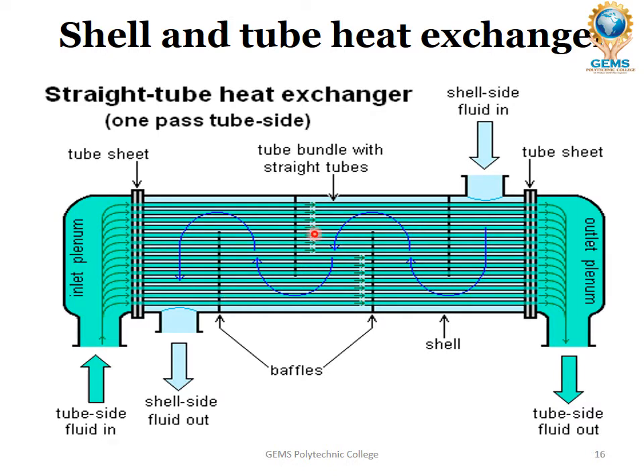Okay, it's a collection of tubes. This fully set up is called the shell, and inside the shell there is a collection of tubes. Inside the tubes one fluid flows, and in between the tubes, on the outer surface of the tubes, the other fluid flows, so that the heat may be transferred.